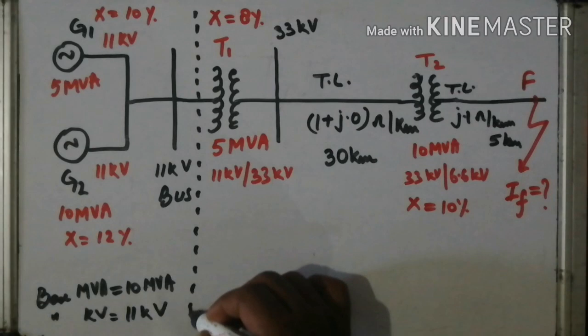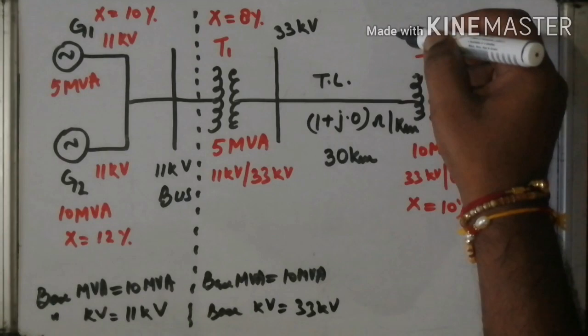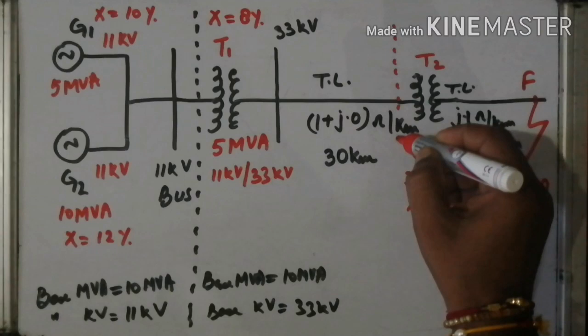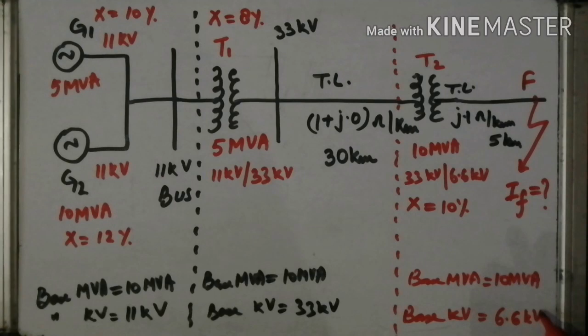Okay, here the base value, that is base MVA, is 10 MVA and the base kV is 33 kV. After that, now at this point, here the base value is same throughout the circuit, but the base kV depends upon the voltage ratio of the transformer, that is 6.6 kilovolt. This one T1 is the step up transformer. It converts 11 kV into 33 kV after the transmission by the TL transmission line.